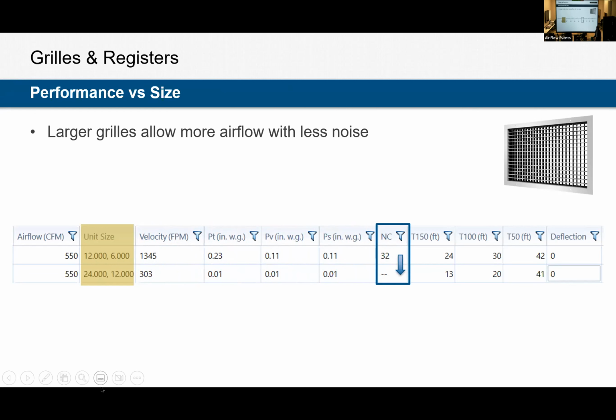And then our sound is also going to be reduced. So we're dropping from 32 NC down to below 15. Substantial reduction in sound with less resistance. But then our throw is almost the exact same. So we're getting a lot of benefits from a larger face with negligible impact to the throw distance. That is because throw is completely dependent on the mass of air that's coming out of that outlet. It doesn't matter how big the outlet is, it's just that mass or that volume of air. It's going to travel about the same distance regardless of the size of that outlet. So the larger the grill, the better. Of course, we can't start putting 5-foot grills on everything, but something to consider in your selection.